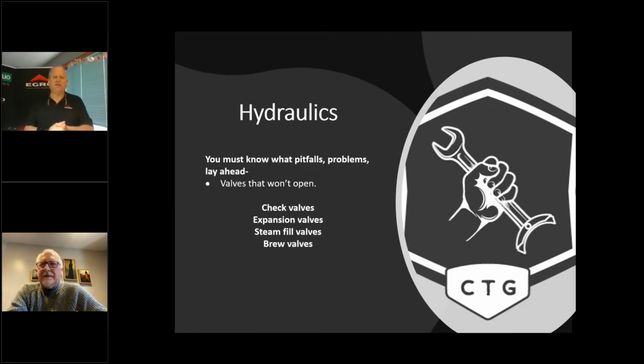Next, valves that won't open. That's obvious. If we're not going to open the valve, like that check valve, that can be an issue. We're starving something, right? Expansion valves, there we start fatiguing metal. We'll talk about expansion valves in a minute. Steam fill valves, I'm sorry, let's just burn the water level down in the tank until we expose the heating element, and now we've got a little fire going on the inside. Don't be alarmed by the word fire. It'll put itself out because it doesn't have oxygen.